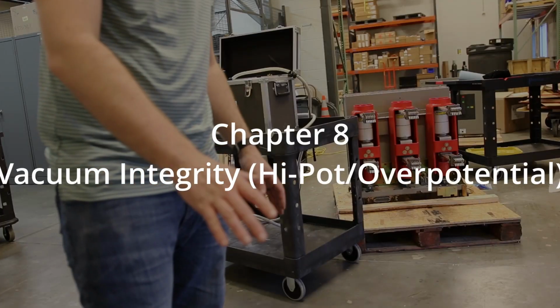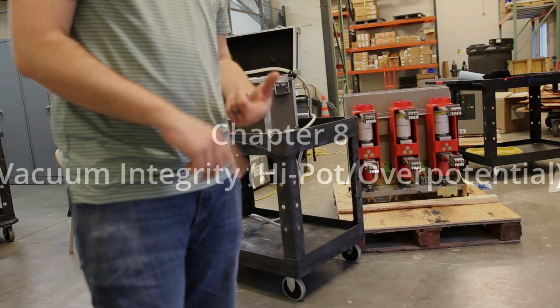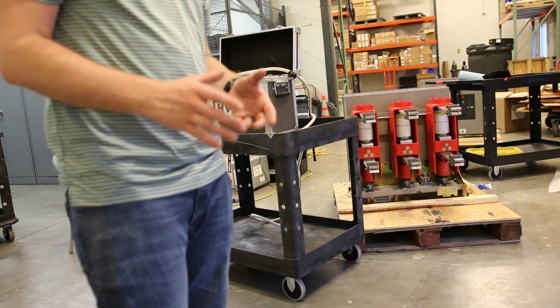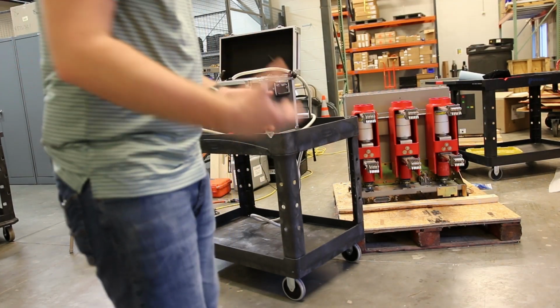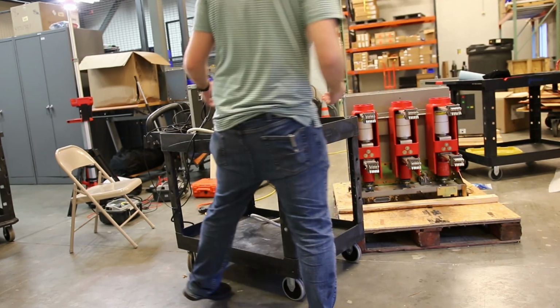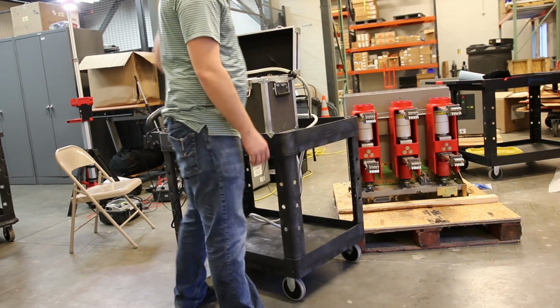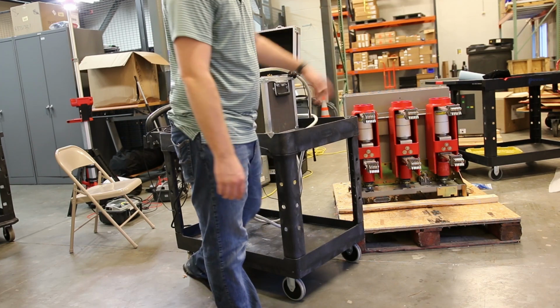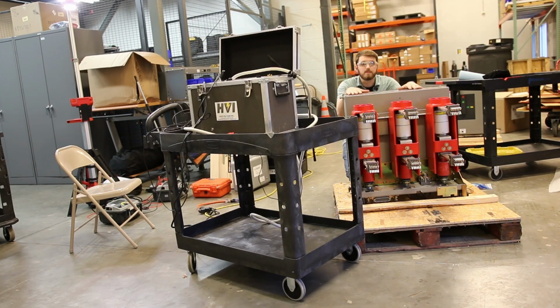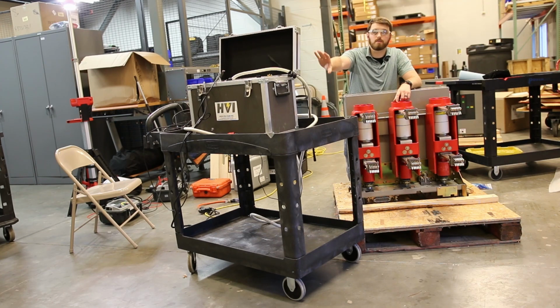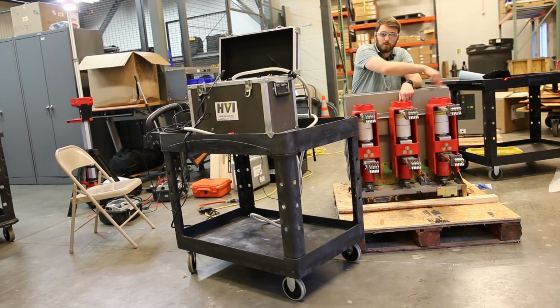Okay, so for this setup, we're doing high pot, which is a vacuum bottle integrity test. Really the best way, the practical way to do this and to do it safely is we put the breaker in the open position, which we're in right now. So with the breaker in the open position, we're gonna hook our hot lead from the high pot to one phase of the lines out of the breaker, or whichever one's most convenient.